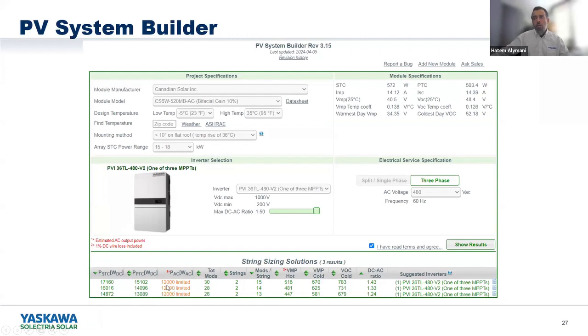But as you see here, we have another warning that is 12000 limited. But this is okay. This is basically just to let you know that your DC to AC ratio is higher than 1.0. Now, there are so many reasons why we want to go higher than 1.0. The standard that I've seen from most designers, depending on the installation area, like here in California, is that they would like to go all the way up to 1.2, 1.25, sometimes 1.3. And that depends on the design, the designer, and the installation requirement. If the overall production is what they're looking for, they will use higher values. If they need more production during the morning hours, or more production during the late afternoon hours, they tend to have a higher DC to AC ratio in order to flatten that duck curve.